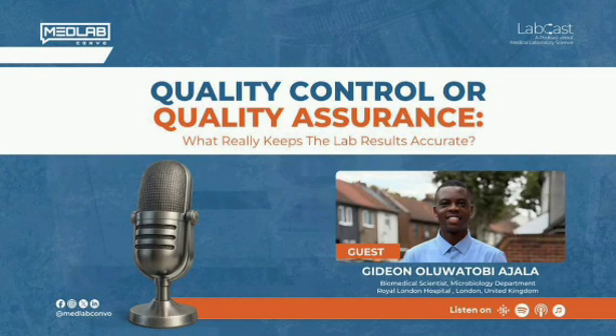There are some that have to be done monthly. There are some that have to be done every 3 months, 6 months, or a year. Let me give you an example. Before I give an example, it all depends on the laboratory and the number of samples you process in a day. For example, in my own hospital where I work, for the urine analyzer, we run over 1,000 urine samples in a day for urine culture and sensitivity. So in that kind of setting, we can't do the QC for the machine once in a day. We do it a minimum of 3 times in a day, in the morning, in the afternoon, and late in the evening.